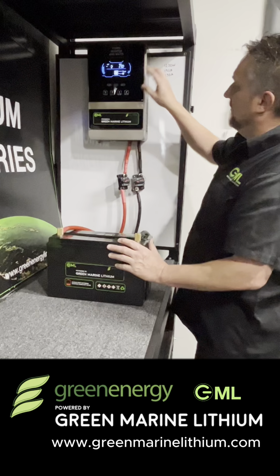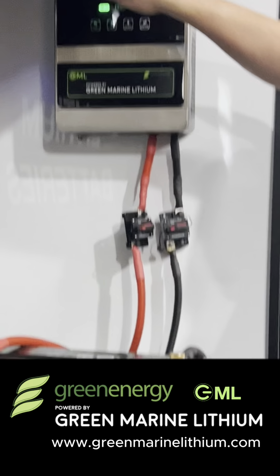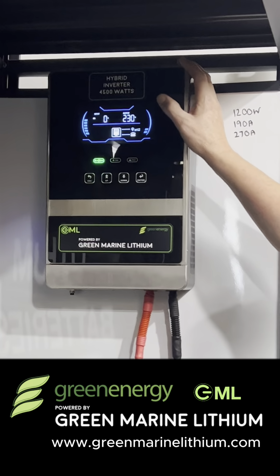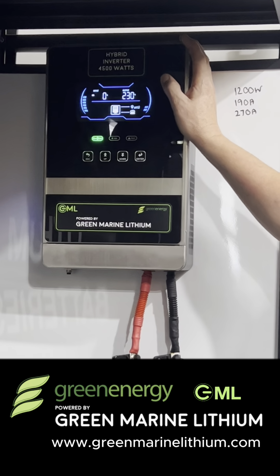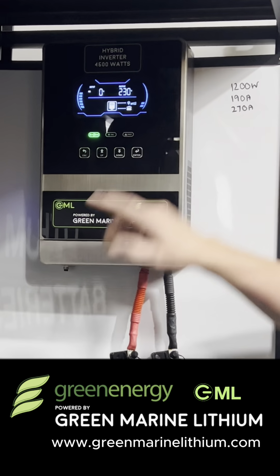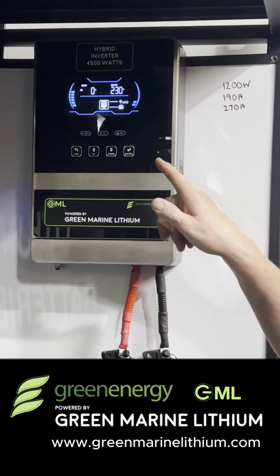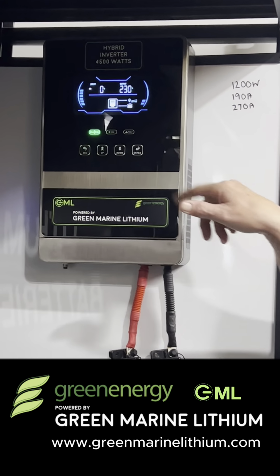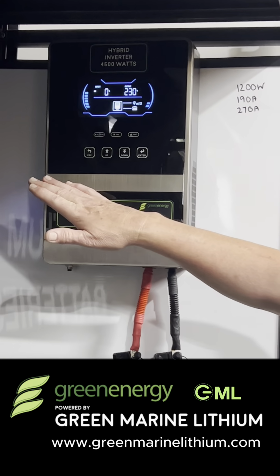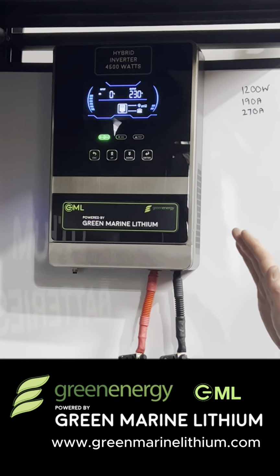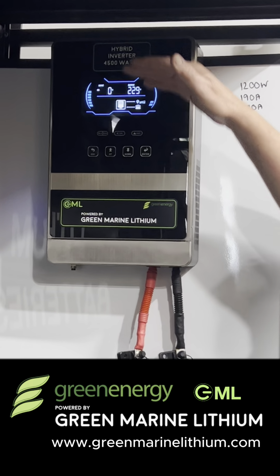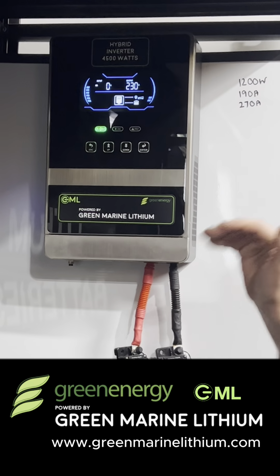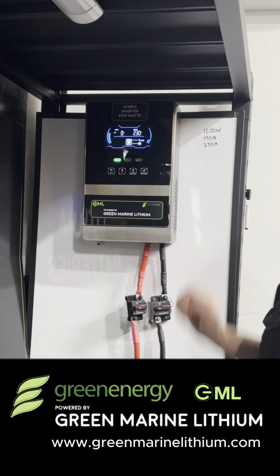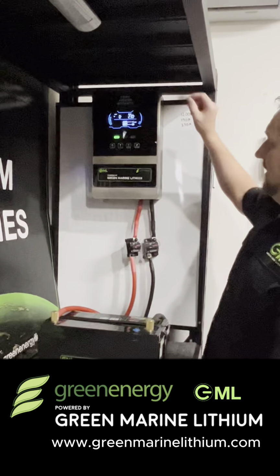This inverter here is a 4,500 watt inverter. Just a thing about inverters - when you buy one, they may label it as 6,000 watts. Read the specifications - that may mean the inverter can put out a maximum of 6,000 watts for a couple of seconds, but then it drops down to 4,000 watts continuous. So the continuous output is what you need to understand.